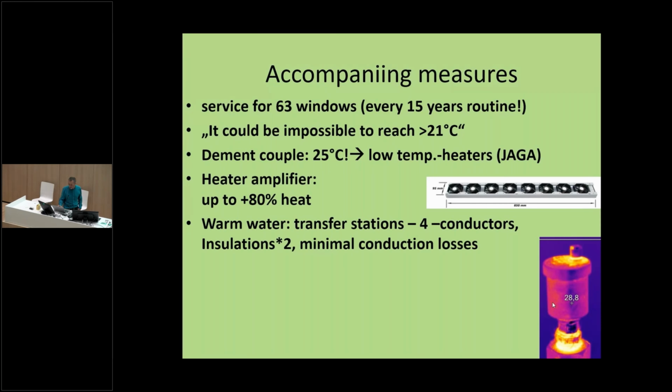Yeah, we have 4 conductors, warm water up, cold water down. In the flats there is a Übergabestation, a kind of heat exchanger, so the fresh water comes with 45 degrees. There's no problem with Legionellen. And we have the second system for heating, and in summer it switches to cooling. So till 15 degrees outside temperature, it's warm water coming up, above 20 degrees cold water coming up.